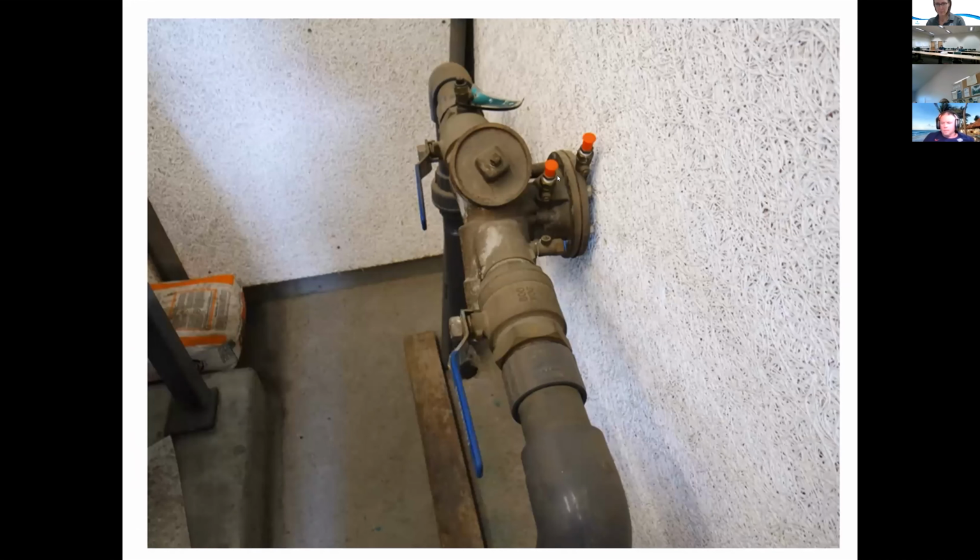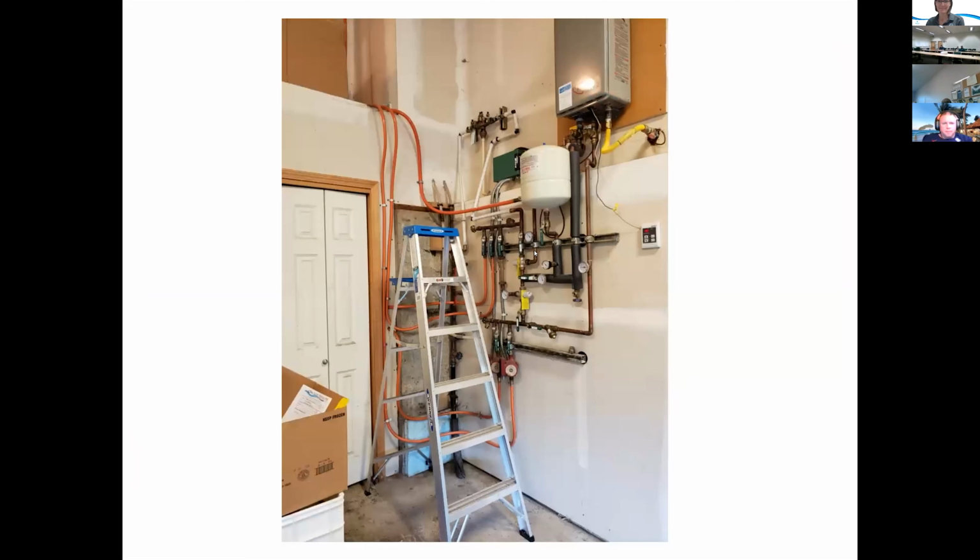How are you supposed to repair this? It fits really nice against the wall, but how are you supposed to get to this and repair it? One of the installation requirements is that if it's going to be higher than 5 feet, you need to have a platform. This really isn't safe working conditions. You'll see it a lot when you go out there. And again, you need to be safe when you're testing backflow assemblies.